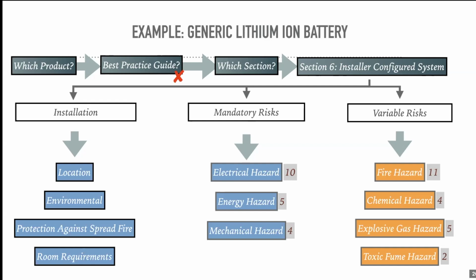So I advise you to look at that risk assessment matrix that they provide in the standard, and it is a requirement. It is a requirement of the documentation too, that you have evidence of a risk assessment. And documentation, like with our other renewable standards, is mandatory. You can't just go, yeah, she's right, mate, it'll work. You actually have to provide an operating manual, a risk assessment, and in the case of battery systems, instruction to the system operator. That's a mandatory requirement, how to operate their system safely.